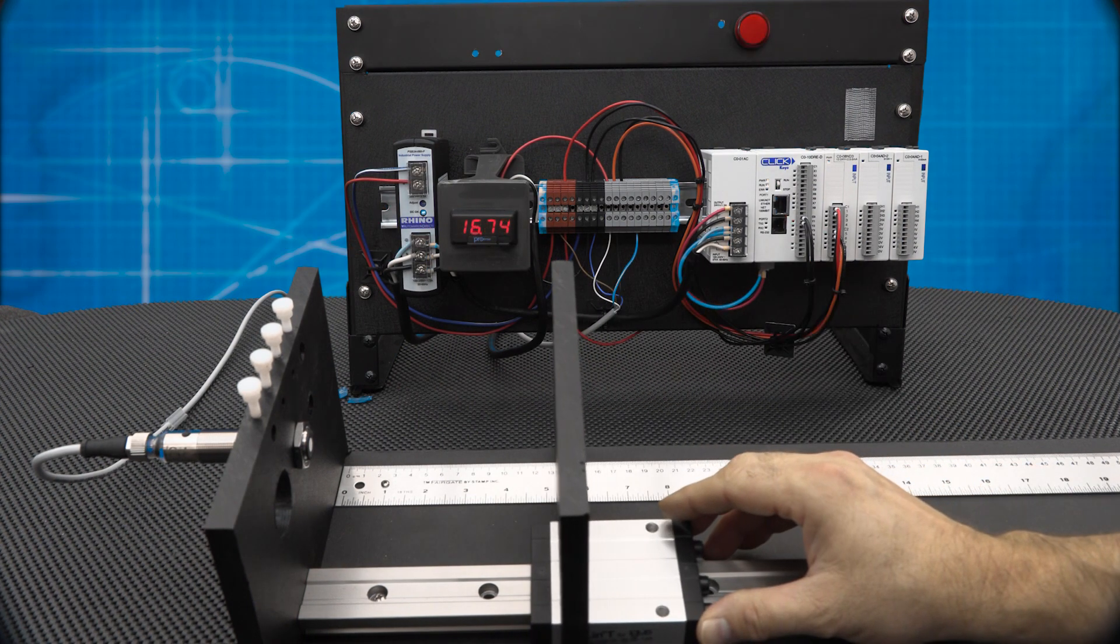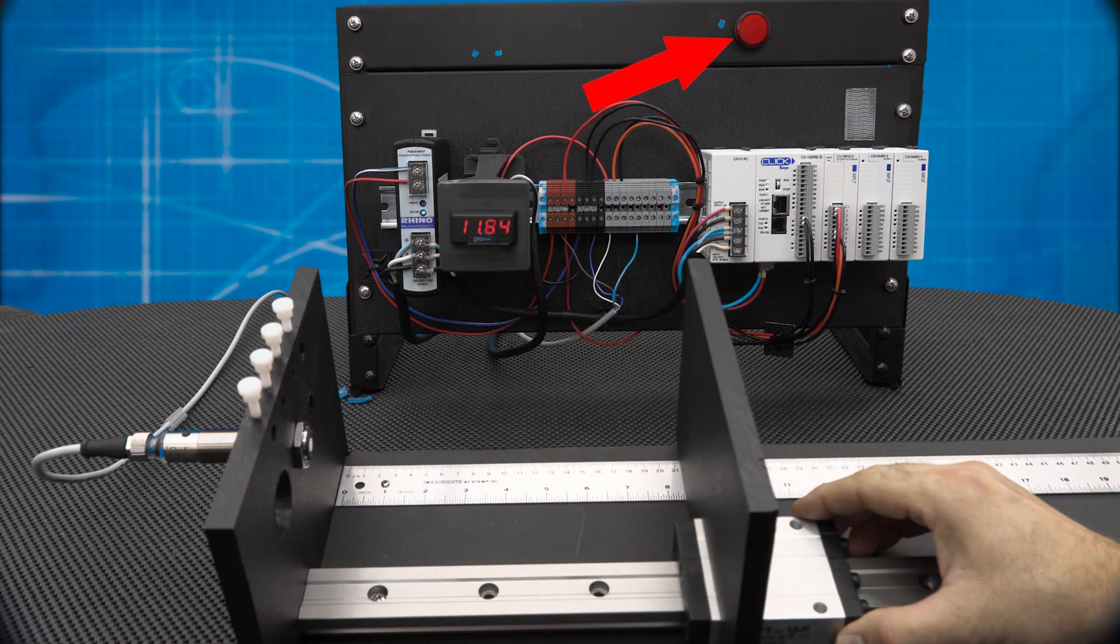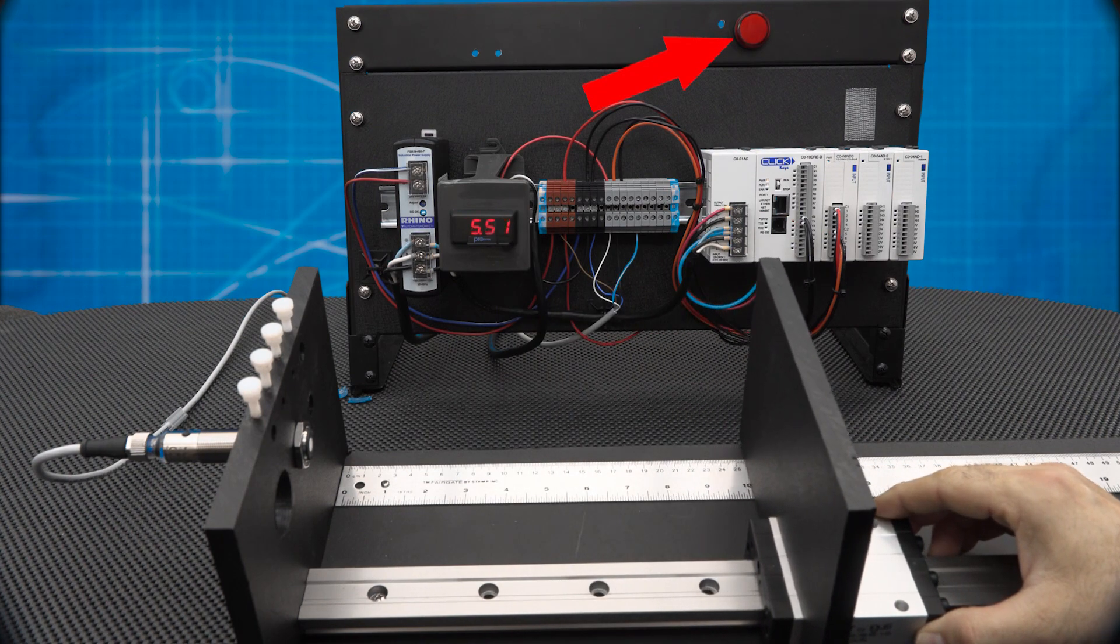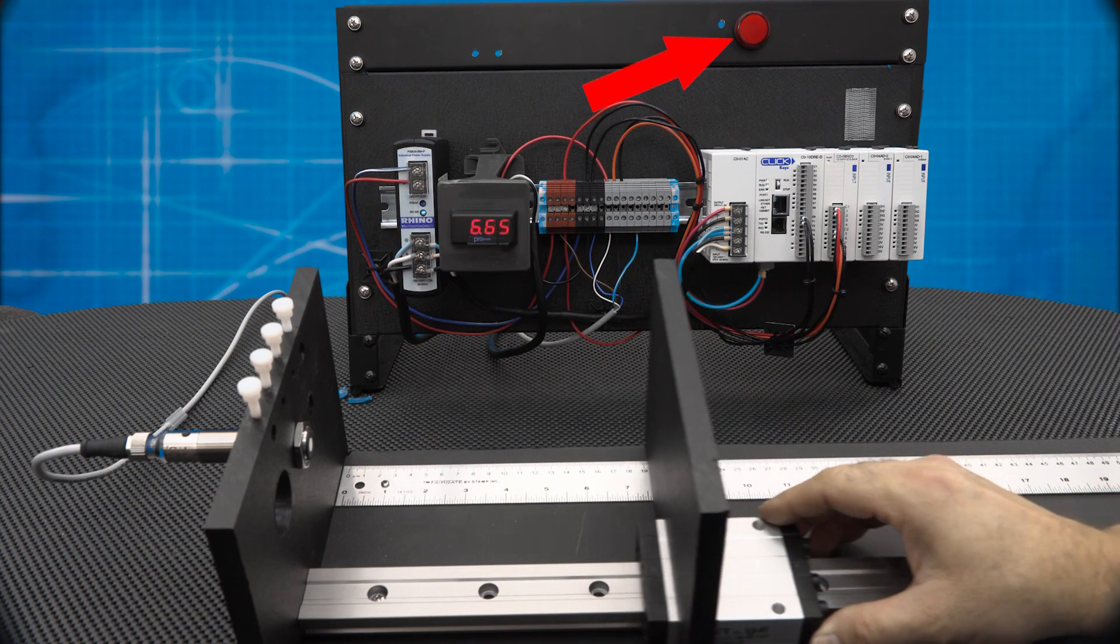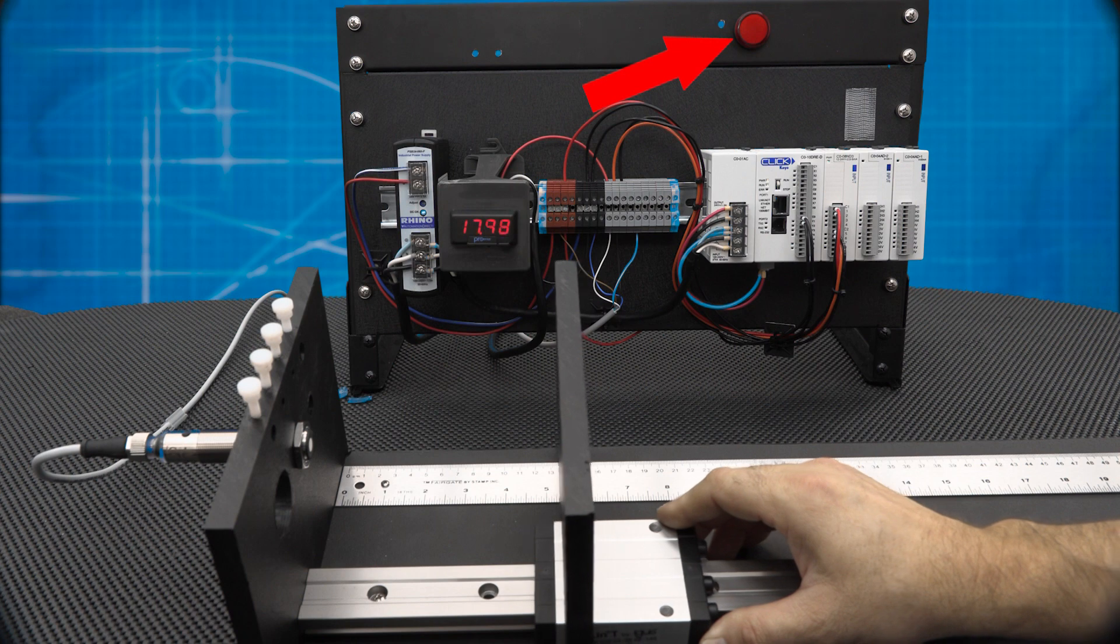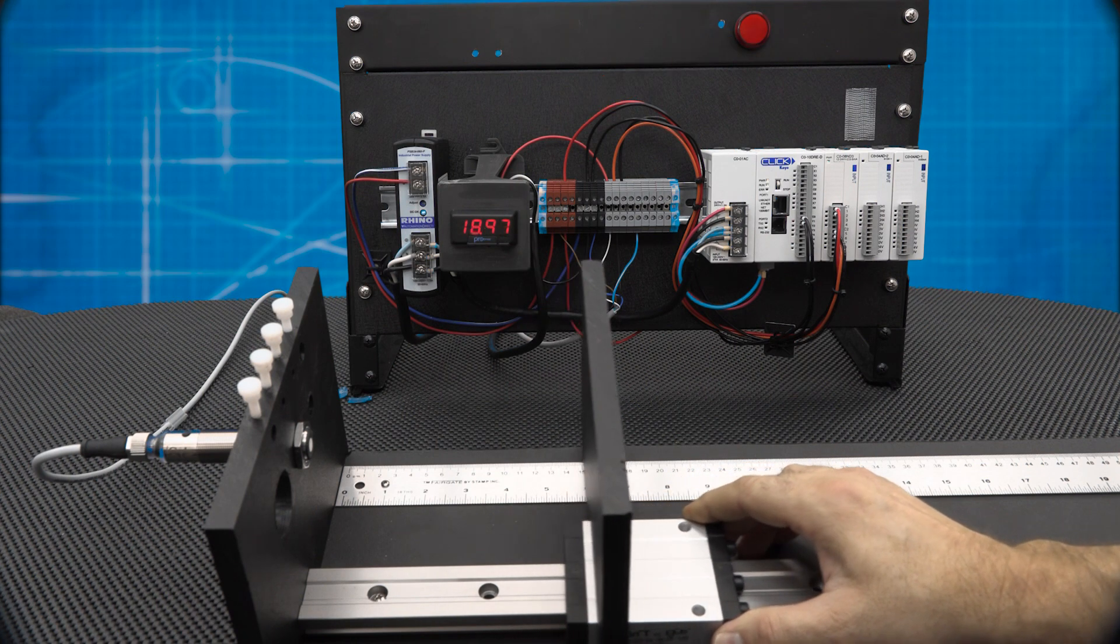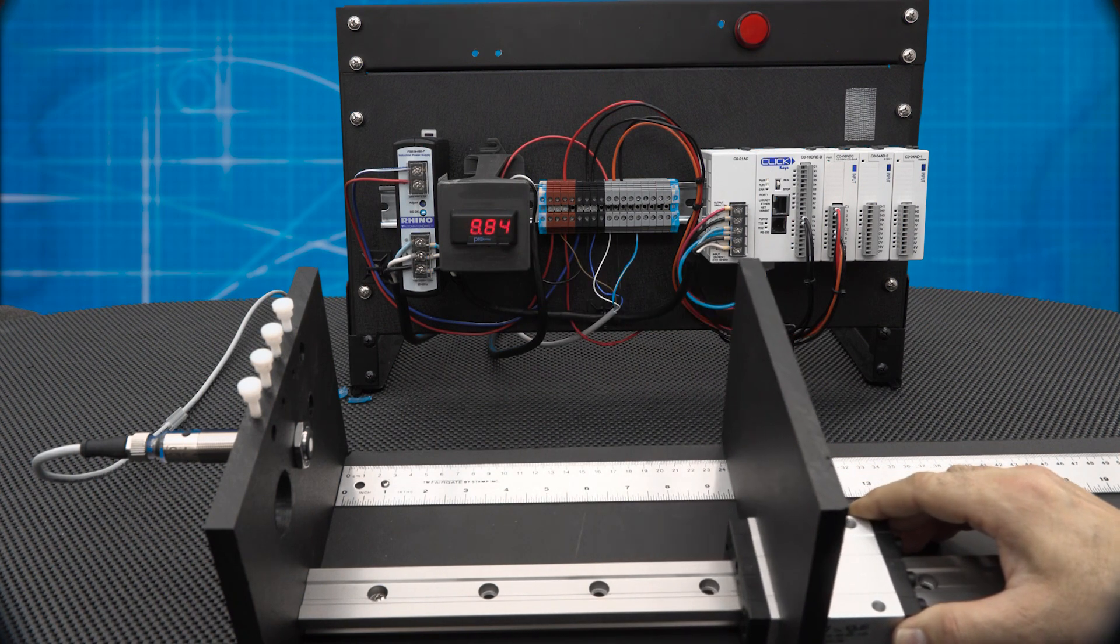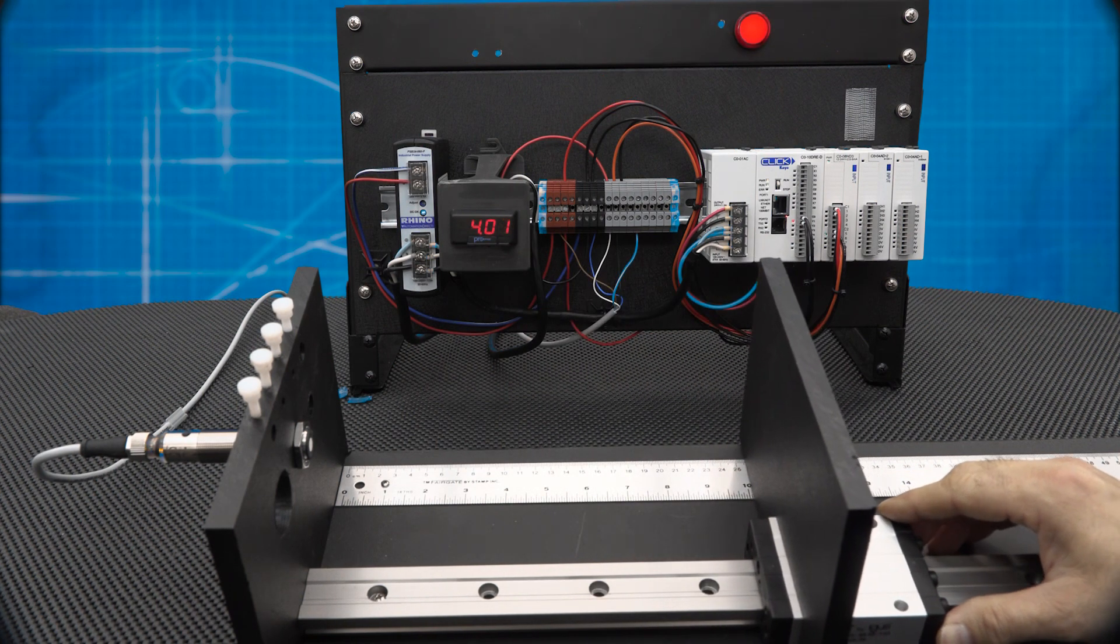The digital output is off from 5 to 10 inches and turns on when we pass either of those limits. This is window mode, normally closed logic, negative slope.